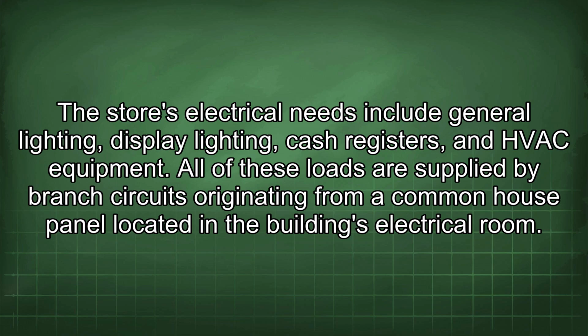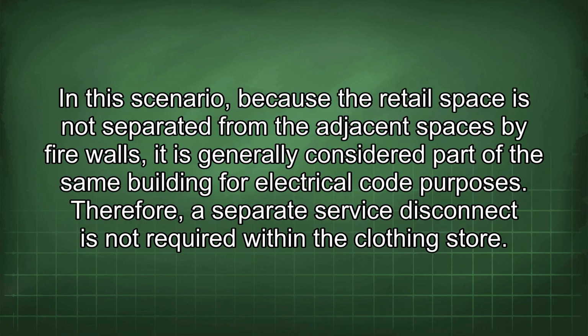All of these loads are supplied by branch circuits originating from a common house panel located in the building's electrical room. In this scenario, because the retail space is not separated from the adjacent spaces by firewalls, it is generally considered part of the same building for electrical code purposes. Therefore, a separate service disconnect is not required within the clothing store.